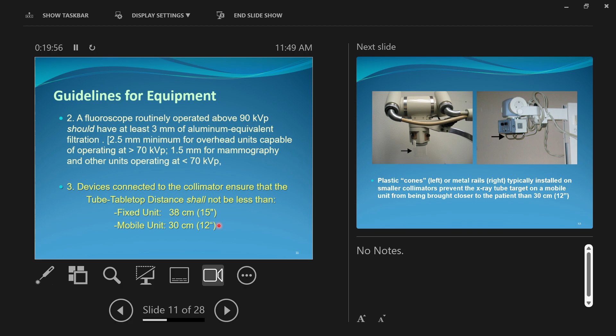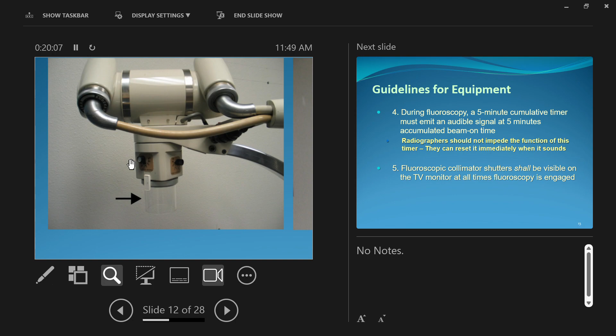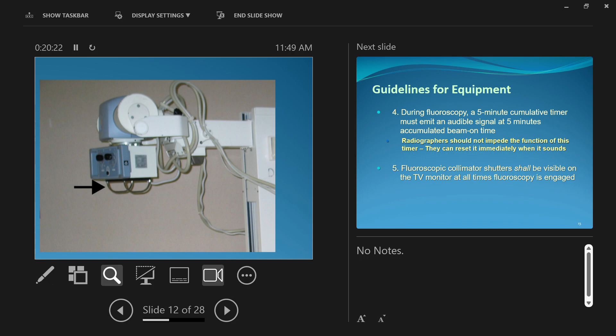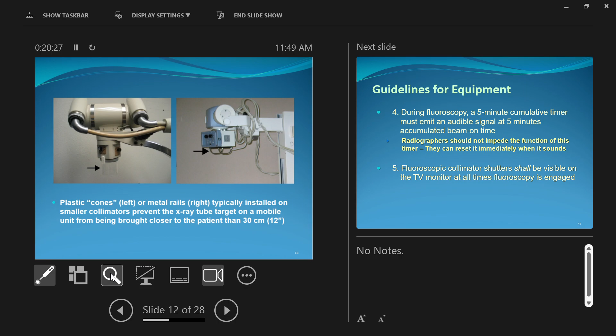We'll often have on mobile units, it's hard to see in this, but let me zoom in, the little clear plexiglass cone gets us that extra distance. And on fixed units, some have rails underneath the collimator box. That's to space out, to make sure there's enough distance between the source of radiation and the skin. The black arrow is pointing at those rails right now. So we have a minimum distance now.